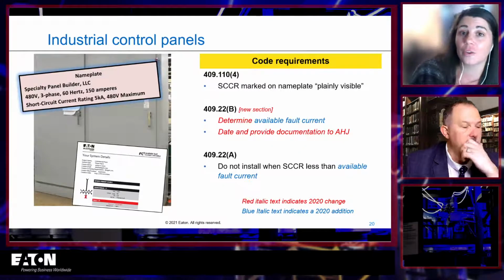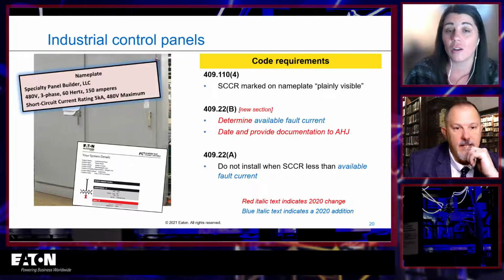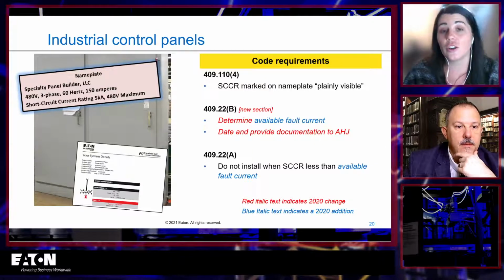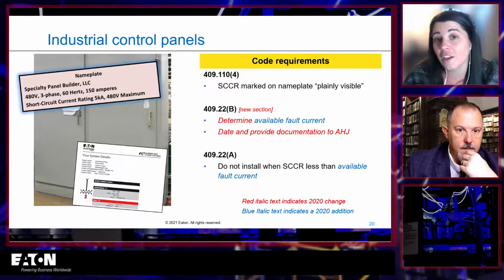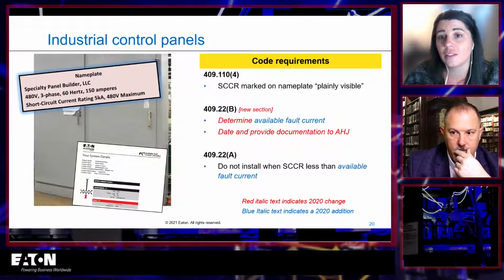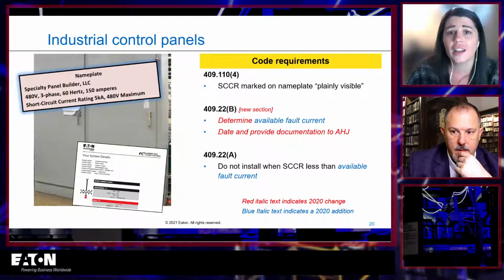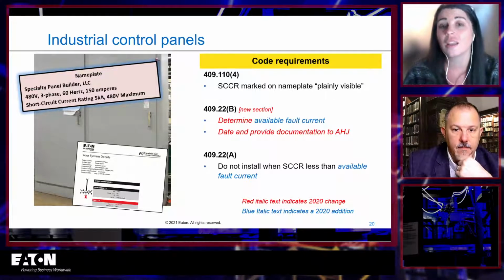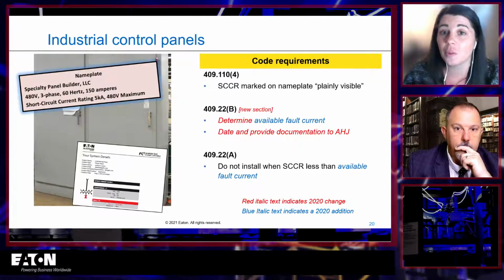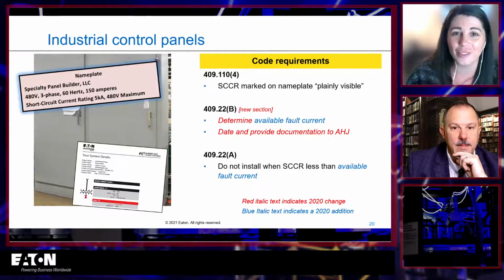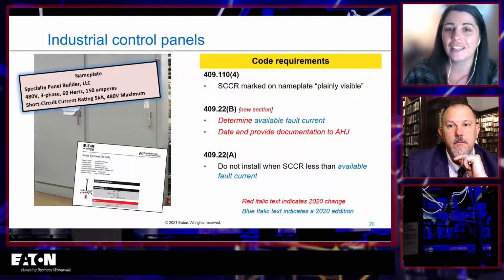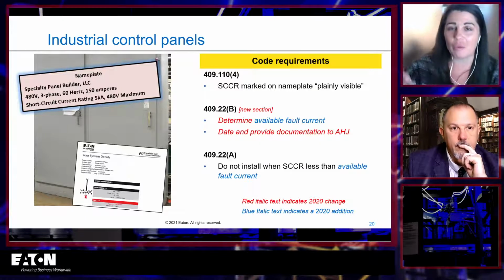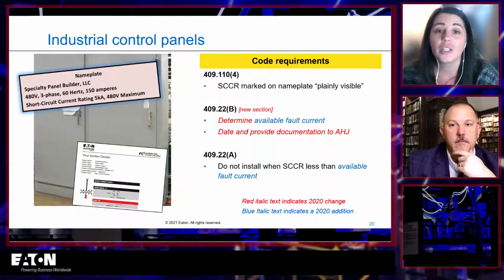Industrial control panels in Article 409. So you've got the SCCR marked on there. That's not new. Determine the available fault current and provide documentation. So that was something added in 2017. I think I have an error through here. So the red is 2017, the blue is 2020. Correct. Basically, the only thing you'll see changed with blue is available fault current. You'll see literally just the phrasing where they made available fault current consistent throughout the whole code.